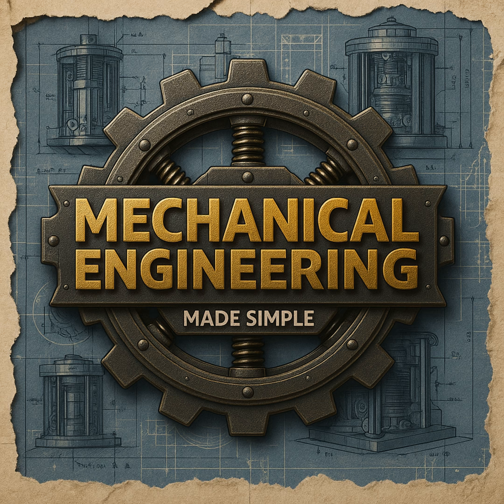That's the idea. And to try and claw back some of that massive energy penalty, good designs absolutely must use something called reset control. This basically tells the system to keep the cold air coil running at the absolute warmest temperature it can while still meeting the cooling and dehumidification needs. It minimizes how much reheating you have to do later. Okay, so reheat is a necessary evil in some cases.